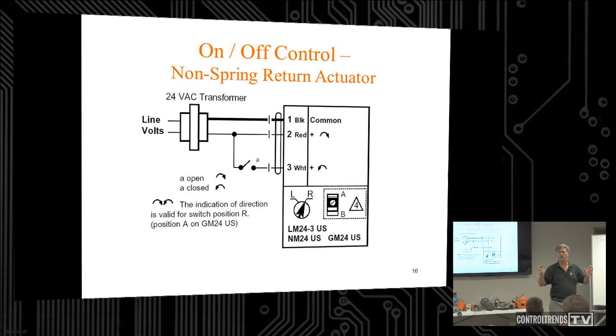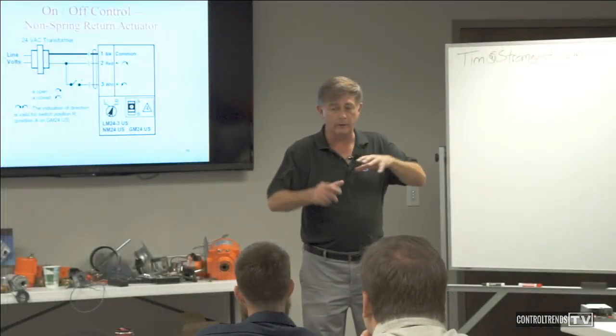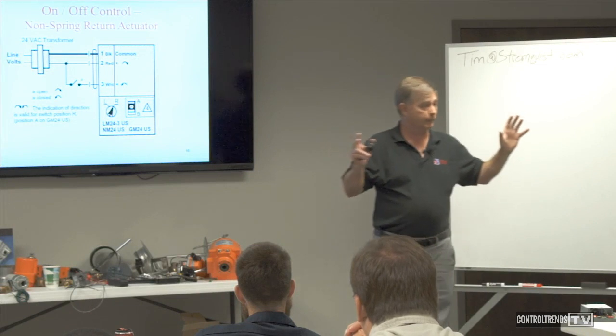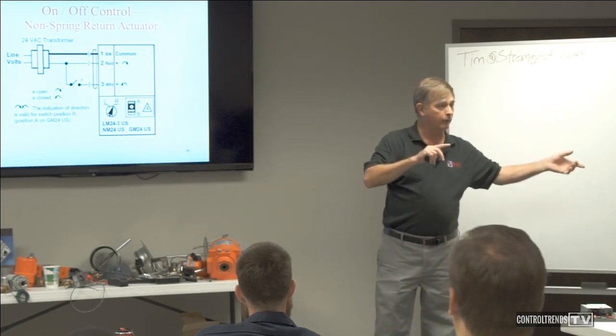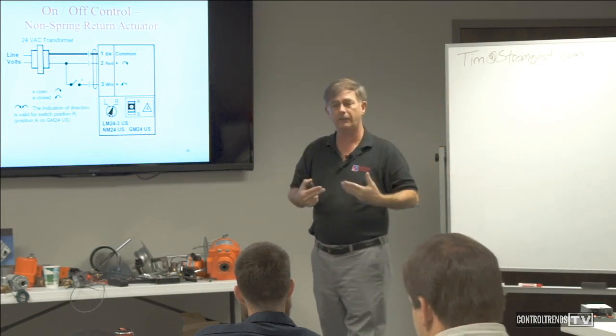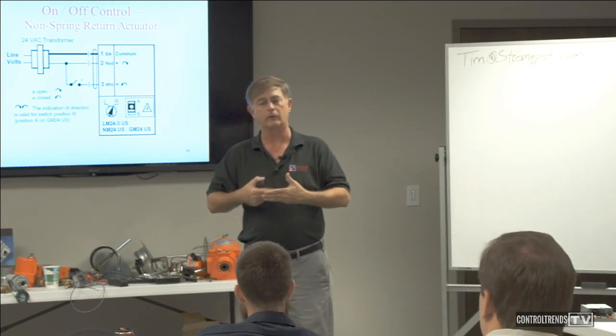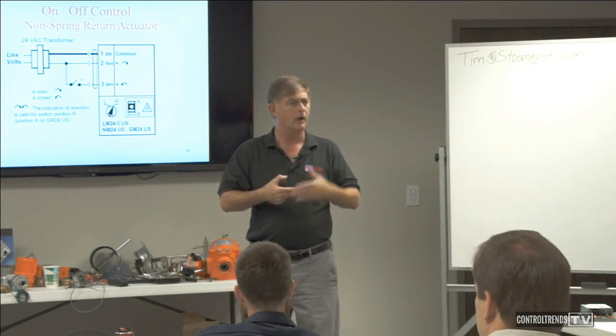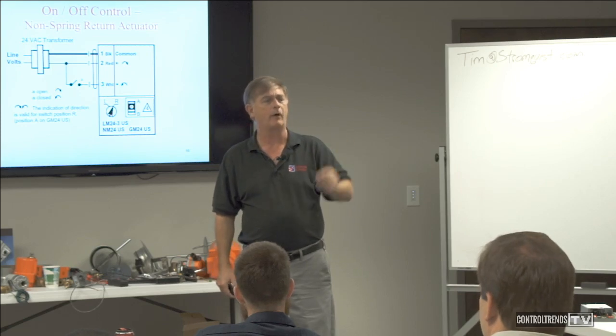By the way, if you want to reverse it, you can switch that action between clockwise and counterclockwise. Again, that's specific to a particular actuator model and brand. So be aware generically of the difference between proportional and floating, and then specifically be very careful and aware of your specific actuator and how it wires.